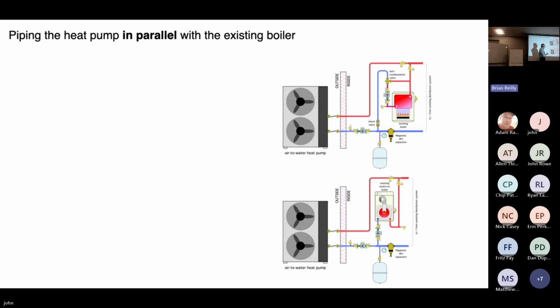Now, that's only going to take 3 or 4 minutes if the boiler was at room temperature. And as the boiler starts to warm up, this valve is going to sense that, and it's going to start opening the cool port. As we open the cool port, that's going to allow some flow to go up through here and out to the system. So what it does is it allows the boiler to warm up in kind of a minimal water volume mass. Okay, this might only have a gallon or 2 of water.